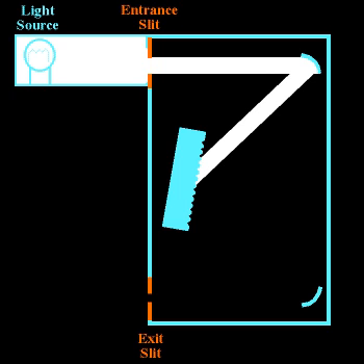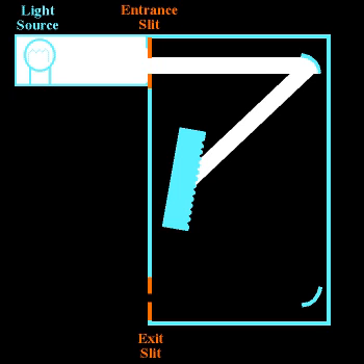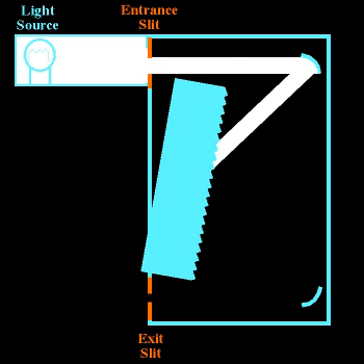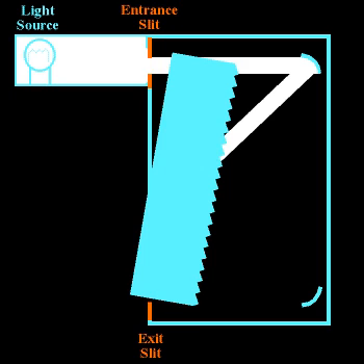If you could put your eye at the grating, you would see bright white light coming from the collimating mirror. The grating surface has very finely etched ridges or grooves with specific spacing. This groove surface is coated with a highly reflective material, such as gold or aluminum, which reflects light with high efficiency. Collimated light from the first mirror, shaped in an image of the entrance slit, reflects off the grating surface.